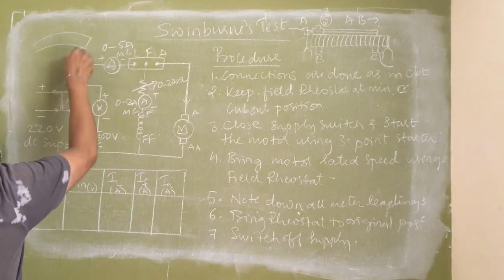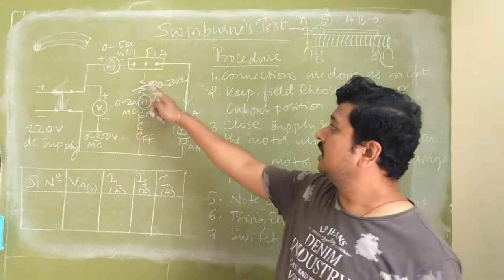Now why do we need a starter? It is not that without a starter I cannot start the motor. Without a starter, if I eliminate this and connect directly to the armature, the motor will start. There is no requirement of a 3-point starter for that. I use a starter for induction motor and DC motor not to assist the starting mechanism. The starting mechanism can be achieved in induction and DC motor without starters also.